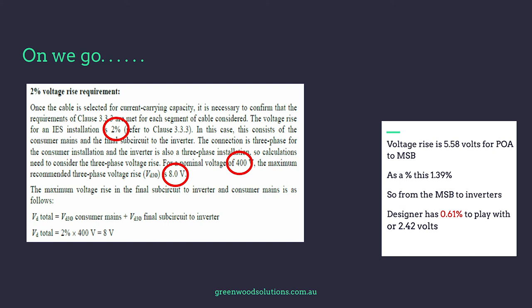From the MSB to the inverters, we've effectively got 0.61% to play with — or 2.42 volts. Be prudent and make sure you understand AS4777.1 and also get really familiar with AS3008.